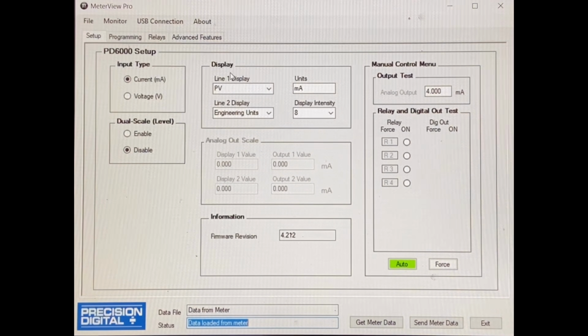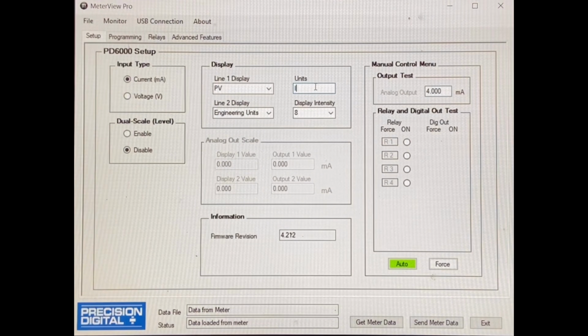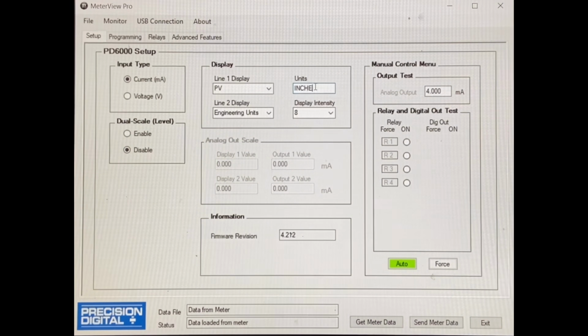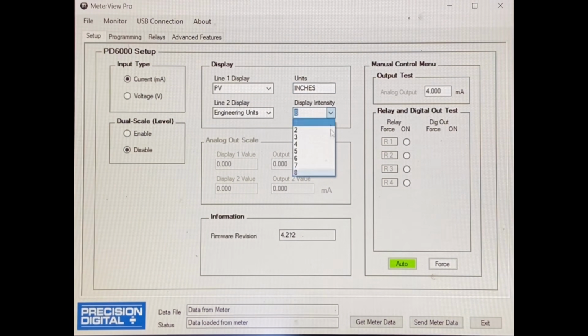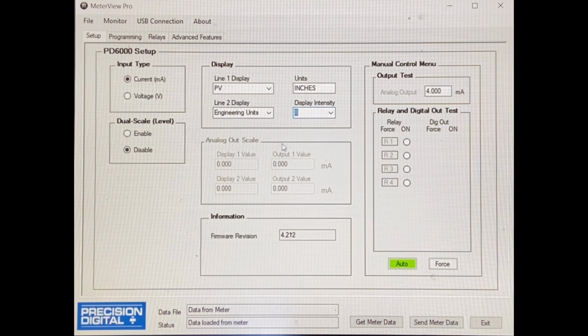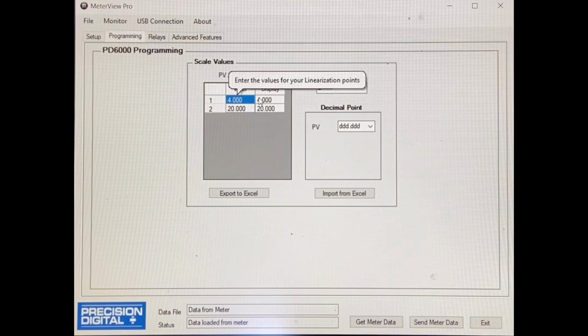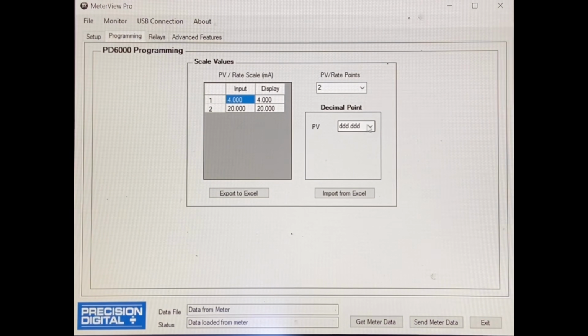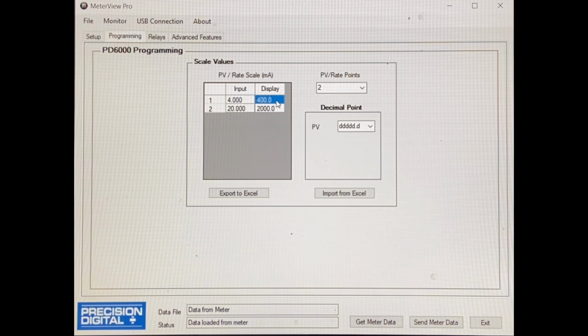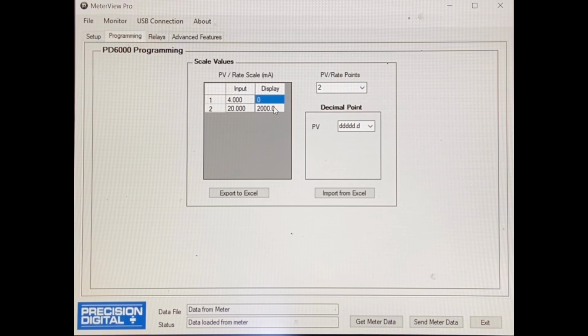Our input type is current or milliamp because that is what we're working with. Our units are going to be inches. You could obviously make this feet or whatever you feel like doing the math to display. We don't have any analog output. We don't really need to mess with anything else there. Here we're going to do our scaling, but always do your decimal point first with these displays. If you don't, you'll have to redo the scaling. It's kind of a pain. That's going to be 0 to 415 inches like I mentioned earlier. I know that's not exact, but it's good enough for poop.